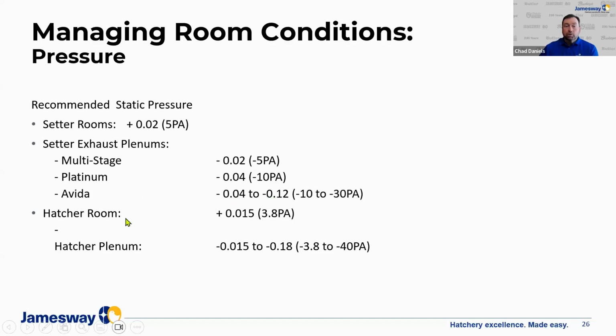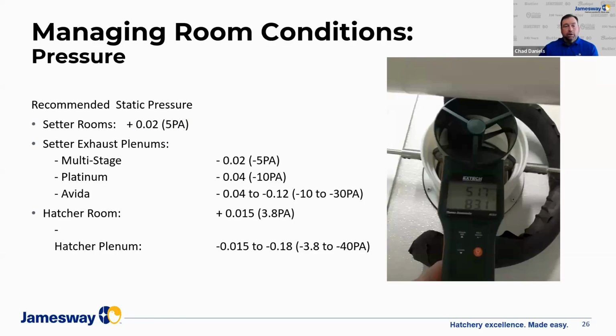Similar with hatcher rooms, where the room pressure should be slightly negative in reference back to, say, the setter room. So it's not as positive as the setter room, because we want to make sure air is flowing from a setter room to a hatcher room and not the other way. But when we look at plenums, there's a big variation in hatcher plenum requirements. Part of that's because of the big variation in the type of hatcher machines available in the market, and in addition, using step programs on rooms to aid cooling the hatcher with additional airflow as you process through a step-down program. Again, I'm using that illustration to monitor airflow through those hatcher machines to make sure I've got that plenum pressure set where it should be.